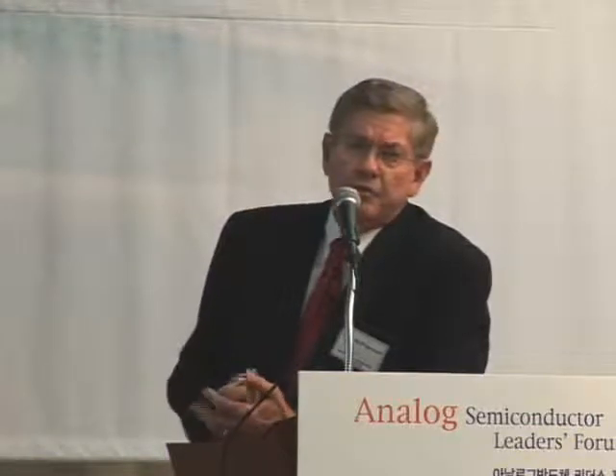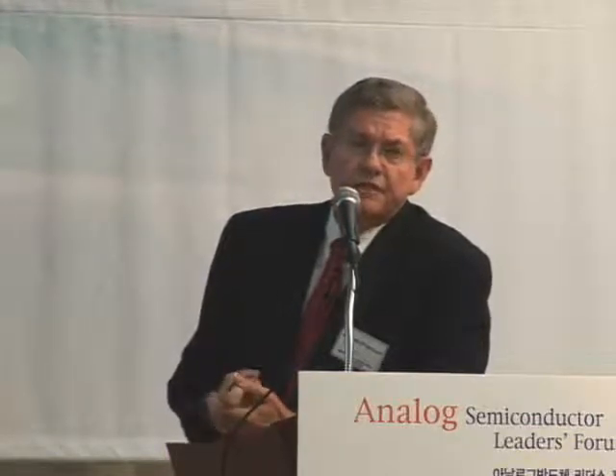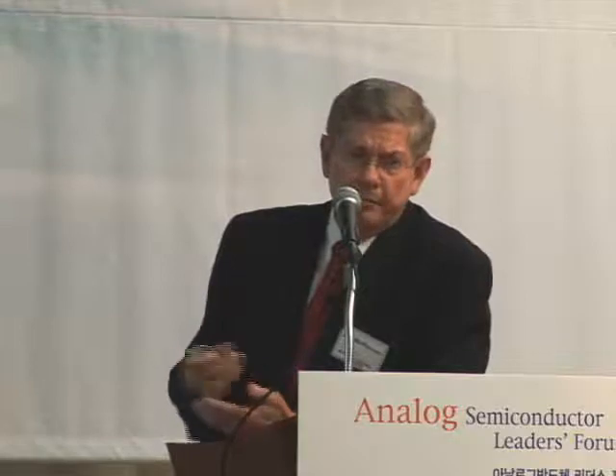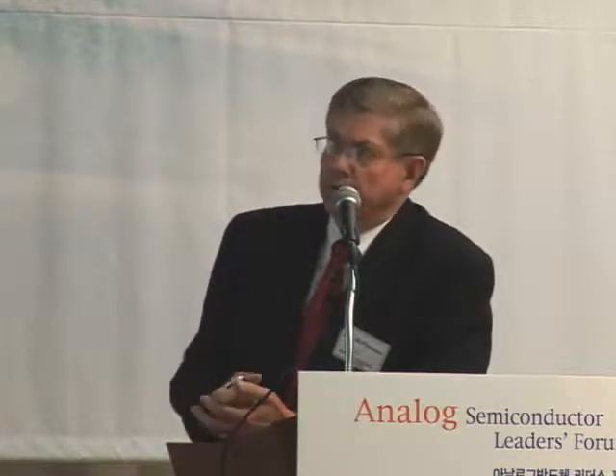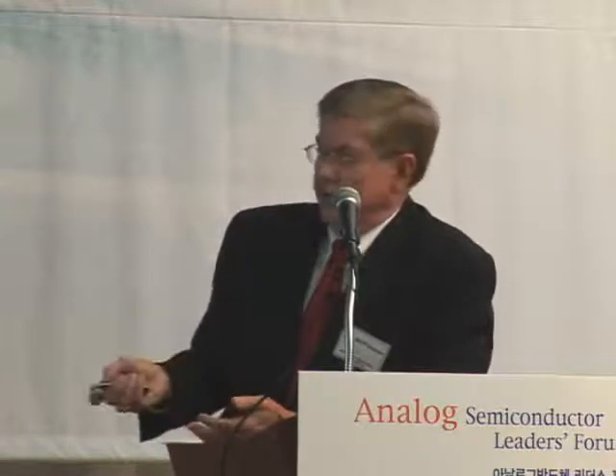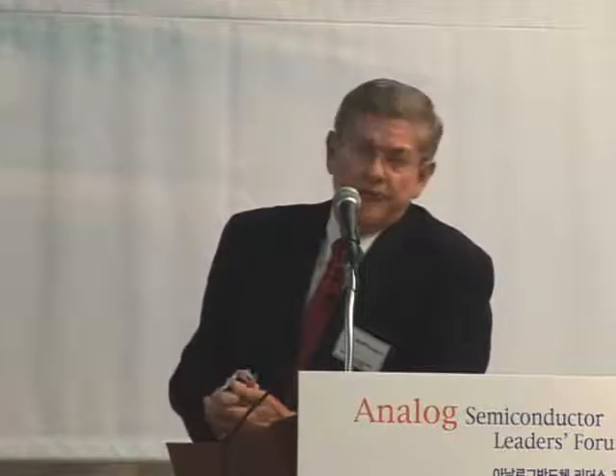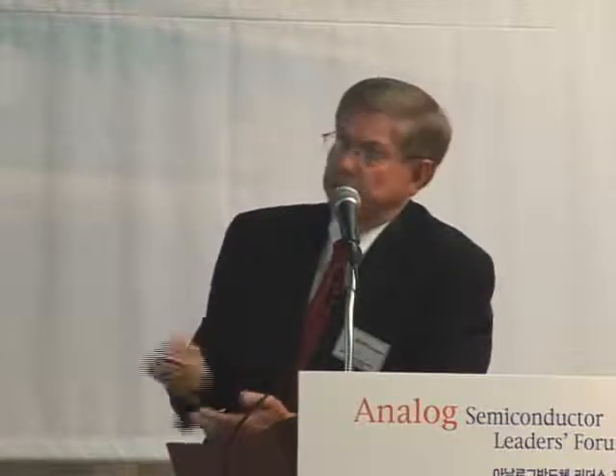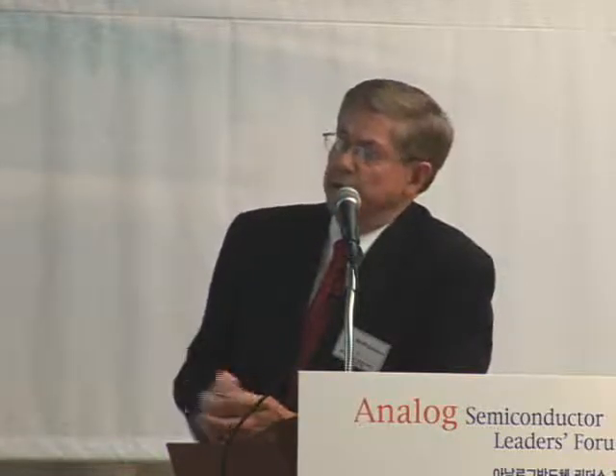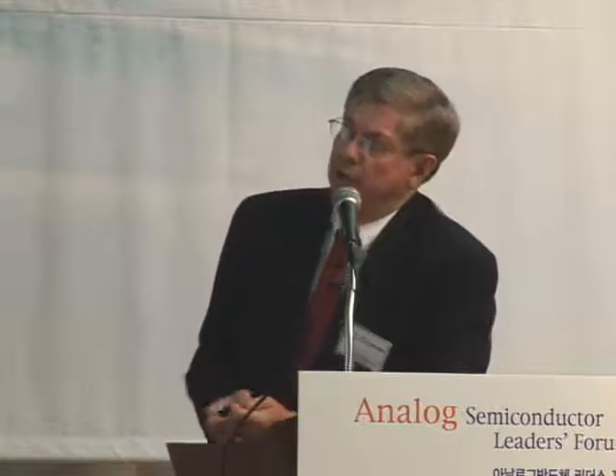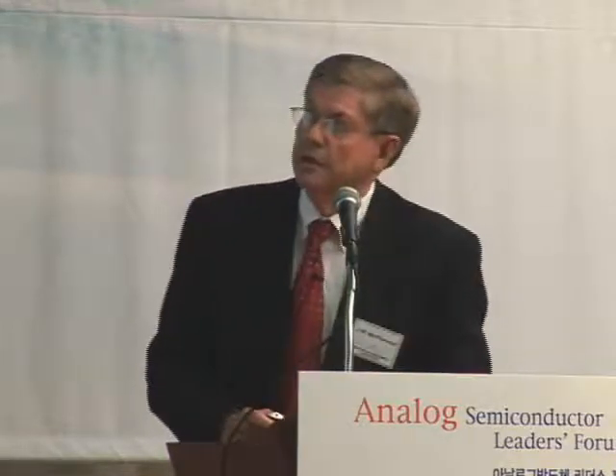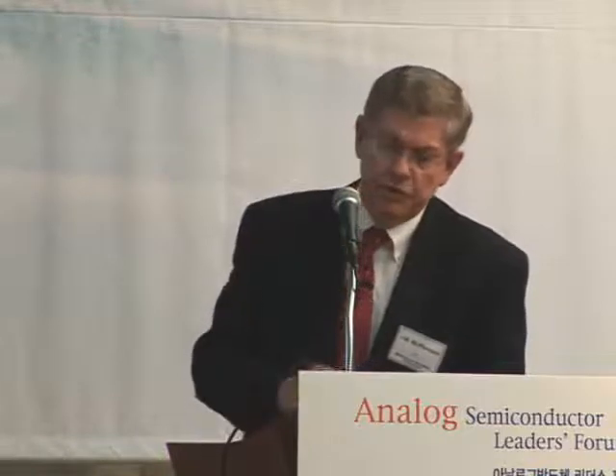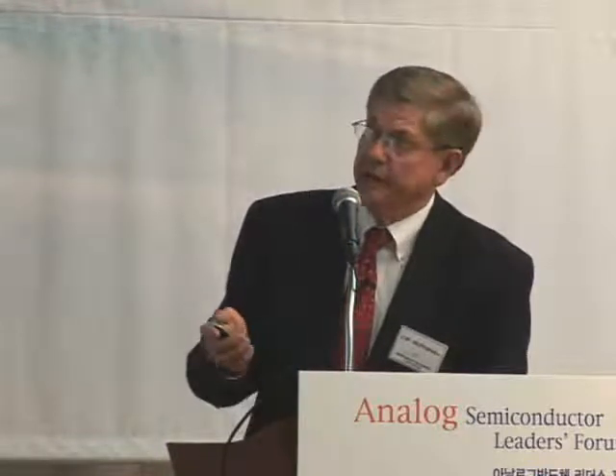So the moral of the story is that if you're doing millisecond pulsing from this power device, you will reach thermal equilibrium. If you get down substantially below a microsecond, you may not reach the maximum we're showing here. But most devices, operating on the order of a millisecond when delivering power, reach thermal equilibrium and reach the maximum temperature.